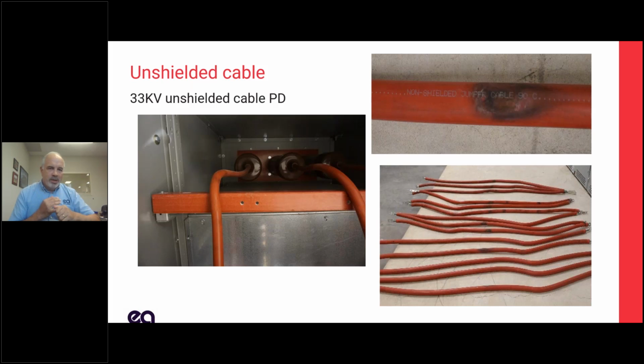The customer looked at it and said, well, I've got an insulator, I've got insulated cable, insulator on insulator, I'm good. That's because we haven't been taught as power engineers to get too excited about electric fields and field control and stress control. And that's what PD is all about. It's electric stress control. In this case, this was poorly done, and someone who's into stress control would know that. Your average high voltage electrician, if they're not into the whole field control and stress control, would not know that. And that's what happened here. A lot of people looked at this and didn't know what was going on.